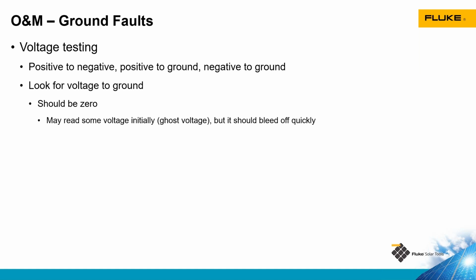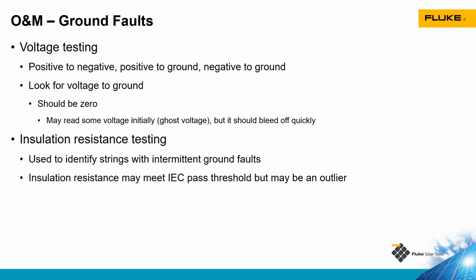Now, we can do a couple things to find ground faults. Voltage testing on our string of PV modules is a way to find a ground fault. We can test between the positive and the negative and get the open circuit voltage of the circuit. Then we can test from positive to ground and negative to ground. There should be zero voltage if the system is working right, assuming that it's a modern inverter and that when the inverter is off, there is no connection between the DC side and the ground. Sometimes you'll see a voltage when you first start testing, and that will bleed off pretty quickly. That's a ghost voltage, and it's not the actual voltage of the string.